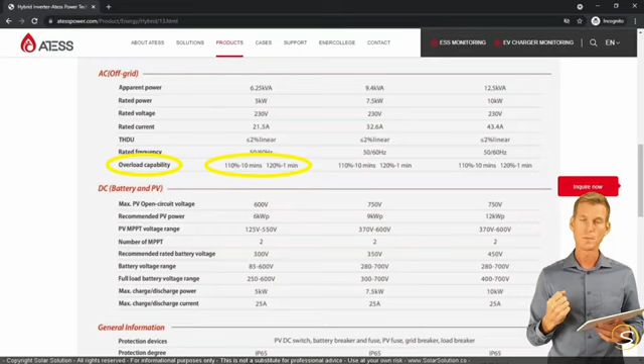And then here in the third section we can find the values for the connection between the hybrid inverter and the solar panels and the hybrid inverter and the batteries, right? So we have here the value on the maximum open circuit voltage from the panels towards the hybrid inverter at 600 volts, which is really good. So you can build really long strings, so very high voltages on your solar arrays. You can also see that it's got 2 separate MPPT trackers, which is really nice. So you can actually make 2 separate groups of panels and connect them both to their own MPPT tracker.